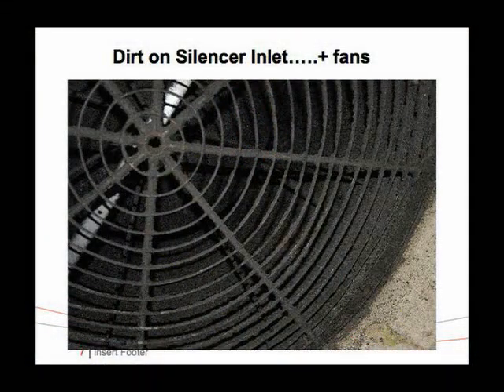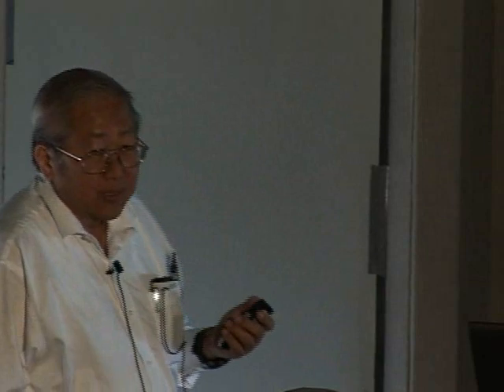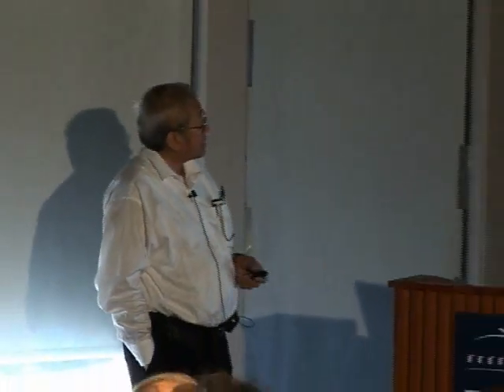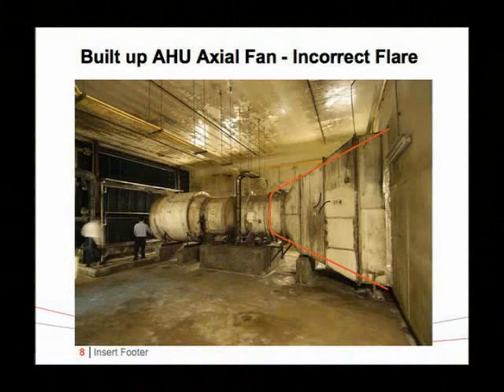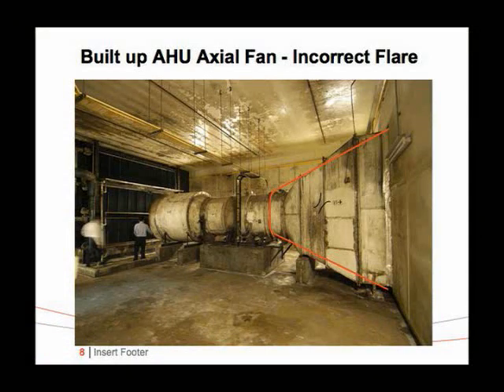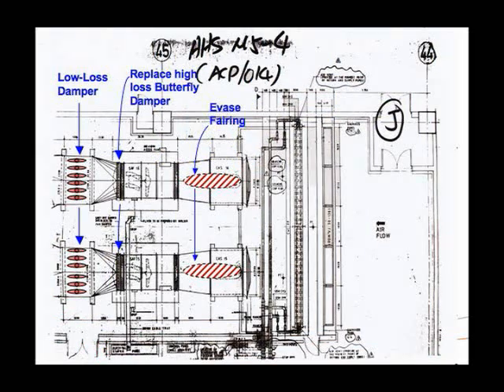And if you go beyond the coil and look at the inlet to the fan, all the dust goes through this toilet roll and builds up. So the aerodynamic efficiency of the fan blades is gone. This dust will go into the ducting system, diffusers, and IAQ and stuff like that. So this is a view of the fan inside, big axial fan, bad outlet flare. I think all of us know you need to do 1 in 7. There's a butterfly damper right after the fan, which is taking away 20% of the pressure development of the fan. So that's not so good. These are some suggested improvements. Take away the butterfly damper, put in normal dampers with streamline and very low pressure drop and stuff like that.